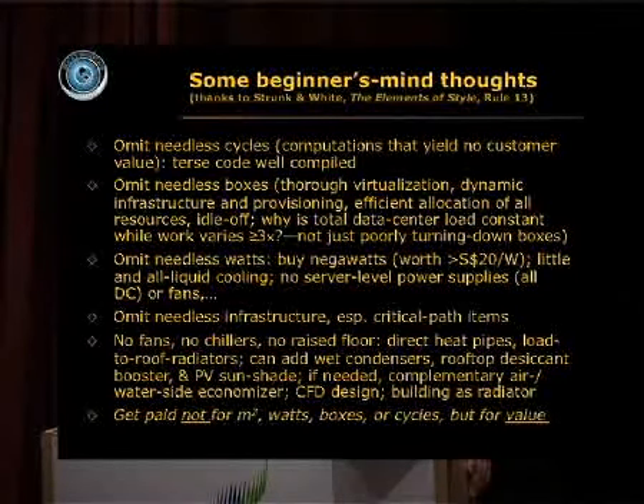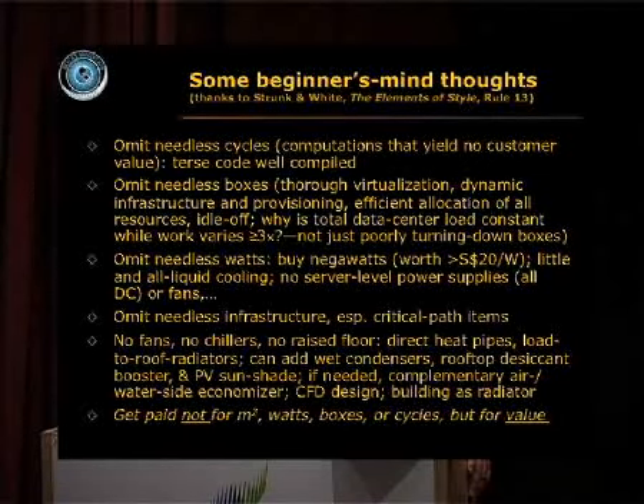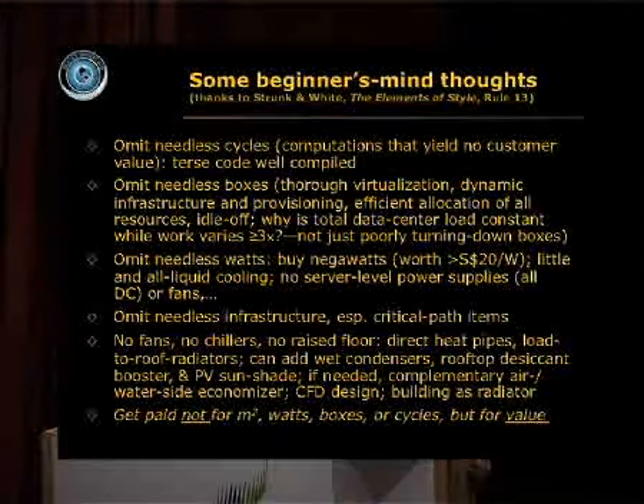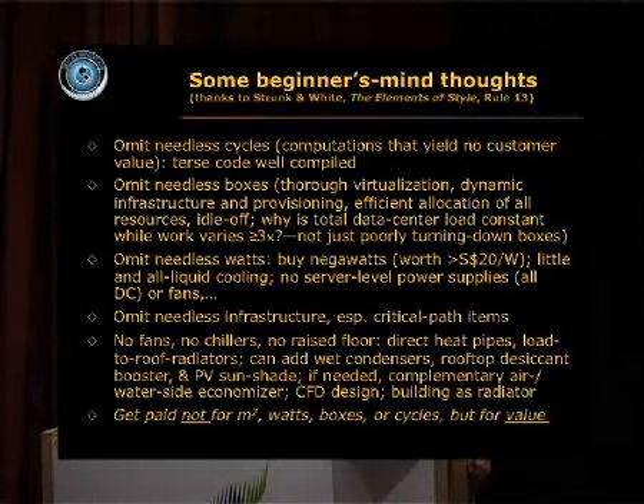So if I apply that philosophy to engineering a data center, and we start all the way downstream, first we'll omit needless cycles, computations that yield no customer value. We will have terse code well compiled. We will then omit needless boxes by virtualization, by using dynamic infrastructure and provisioning, so we turn things on and off according to what we need at the time. We will efficiently allocate all resources and turn off whatever we're not actually using. Why is it that our data centers have a constant load while the workload on them, the IT load, varies by at least a factor 3? There's something wrong with this picture.